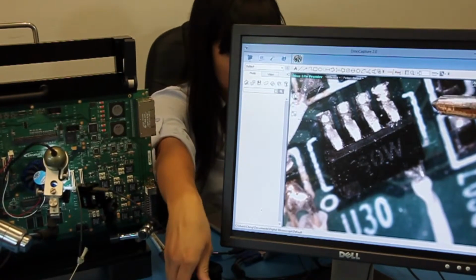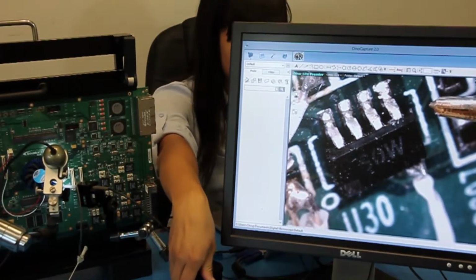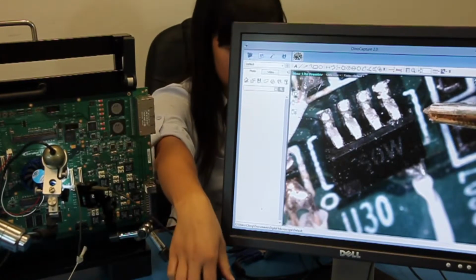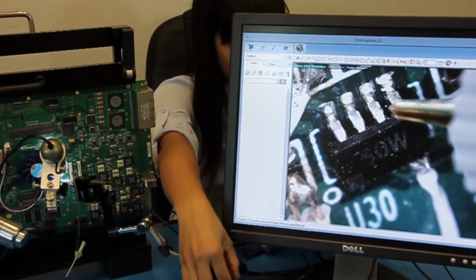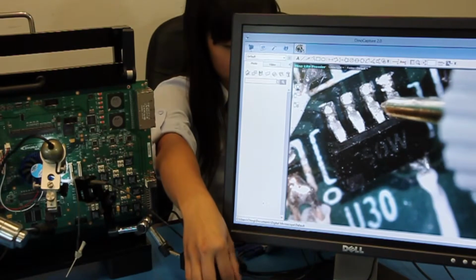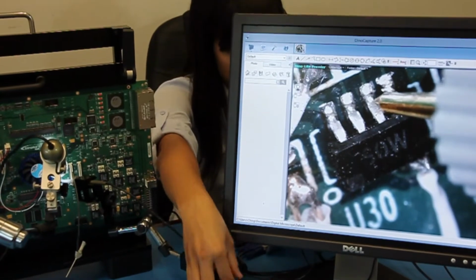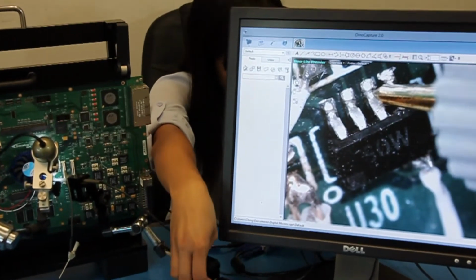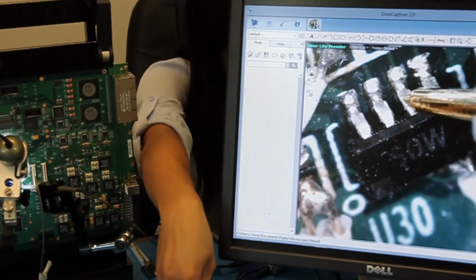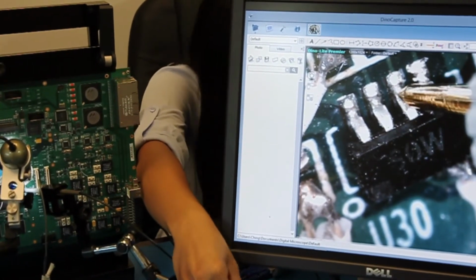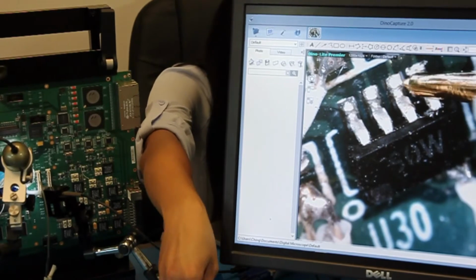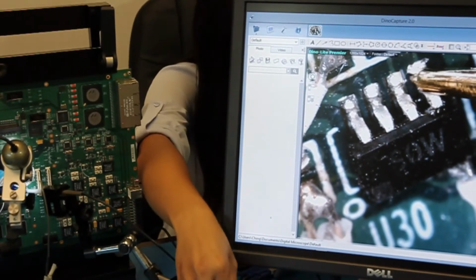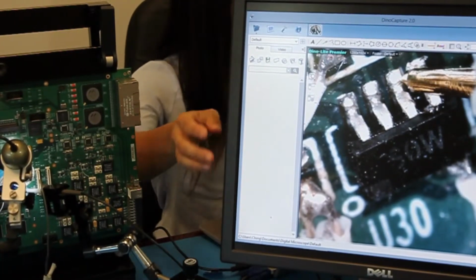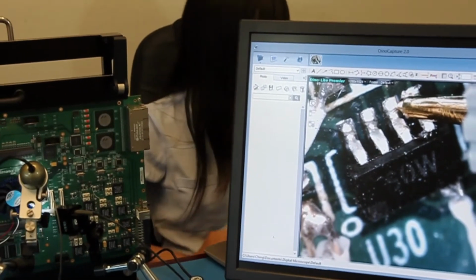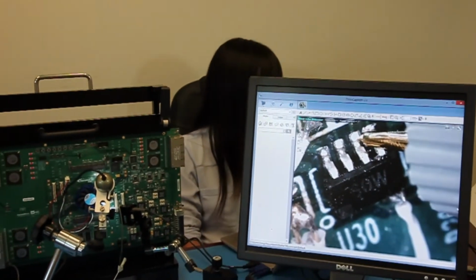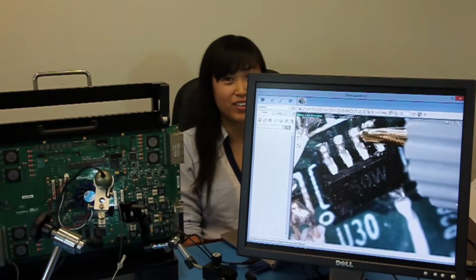So this is the Z screw that moves the tip up and down, and to the side is the Y screw that moves the tip sideways, left to right. And lastly, behind is the X screw that moves the tip forward or backwards. And has made contact. You can see clearly when the probe tip is touching the test point on the screen now.